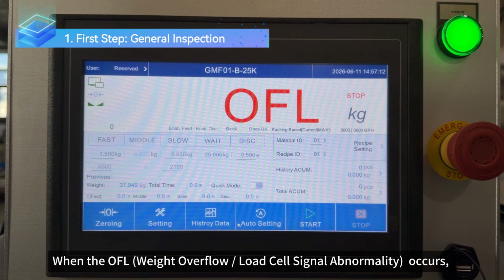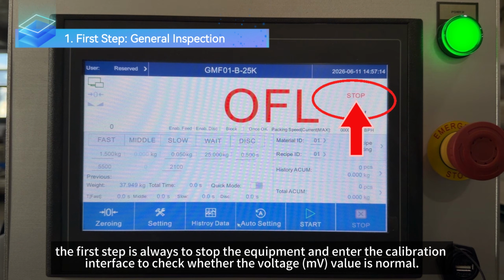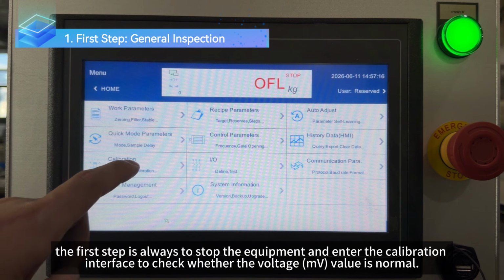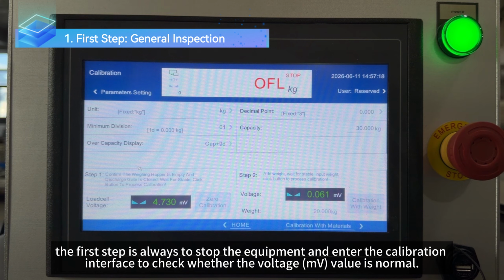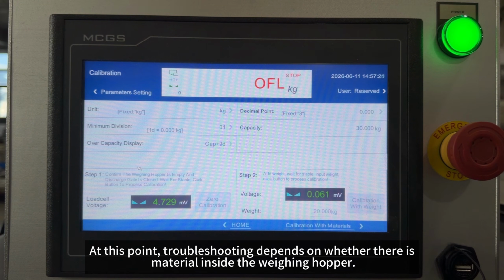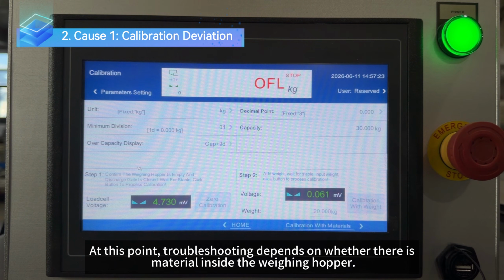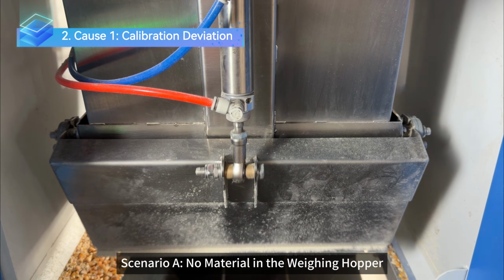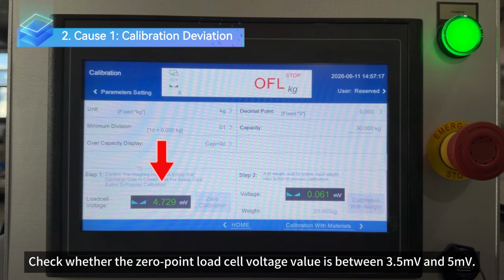When the OFL occurs, the first step is always to stop the equipment and enter the calibration interface to check whether the voltage value is normal. At this point, troubleshooting depends on whether there is material inside the weighing hopper. Scenario A, no material in the weighing hopper. Check whether the 0-point load cell voltage value is between 3.5 mV and 5 mV.